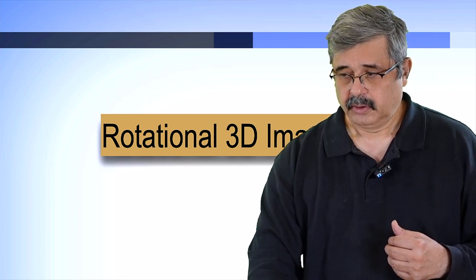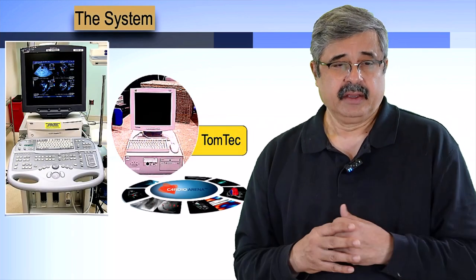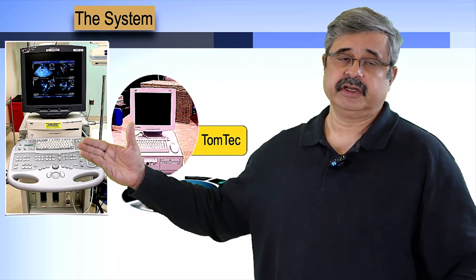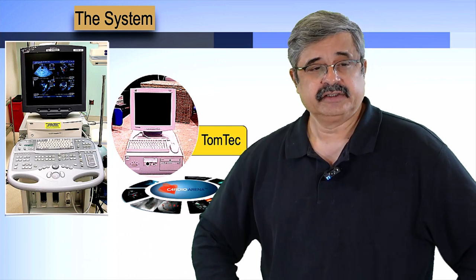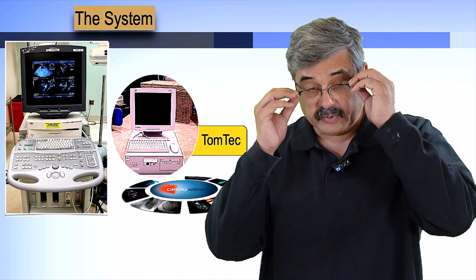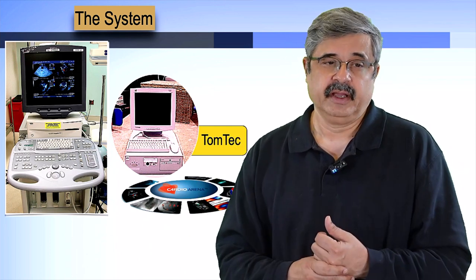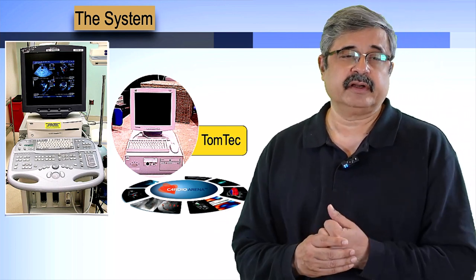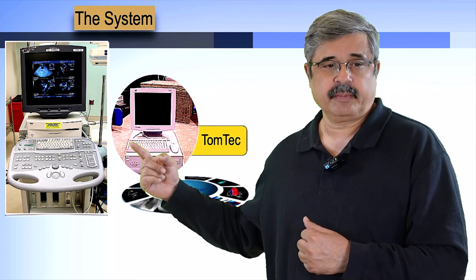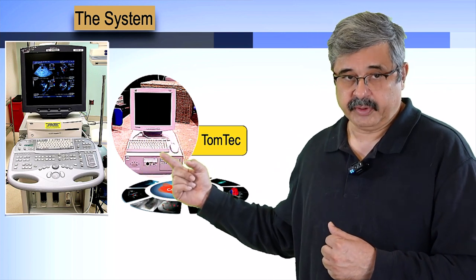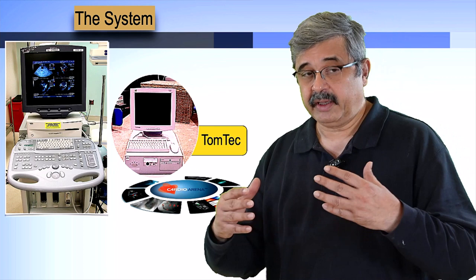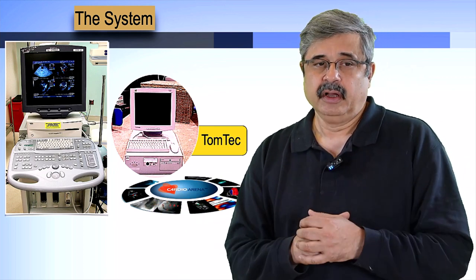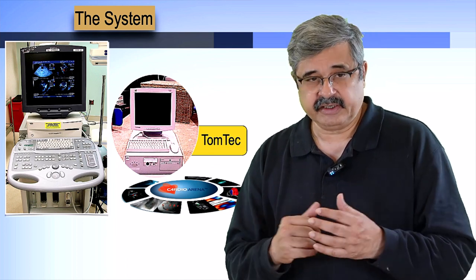This was the system most commonly used for rotational three-dimensional imaging: the Siemens Sequoia C512. In its own right, it was a phenomenal 2D system. It had a V6M probe capable of two-dimensional imaging but was not capable of rotational three-dimensional imaging unless coupled with a TomTec computer. This TomTec computer could be incorporated in any two-dimensional system but was most compatible with the Siemens Sequoia C512.